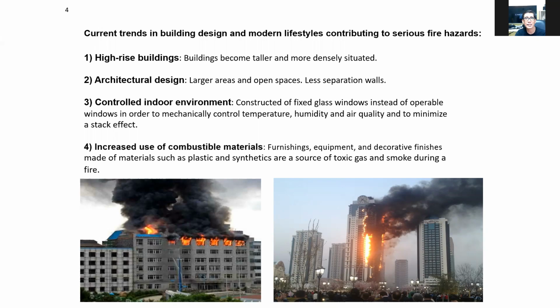So because of the large areas, like if you're going to a mall or a convention center, there are very large areas and high capacity of persons inside, and there are fewer separations of wall. If in case there will be fire, the fire can go to the other side of the room or the other side of the wing of the building because of fewer firewalls that will separate each building or each zone. So another one is controlled indoor environment, like construction of fixed glass windows instead of operable windows in order to mechanically control temperature, humidity, air quality, and to minimize the stack effect.